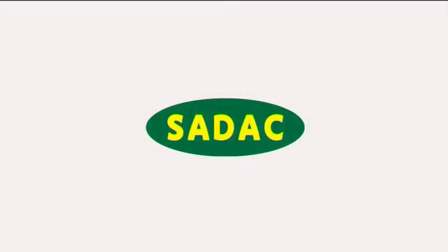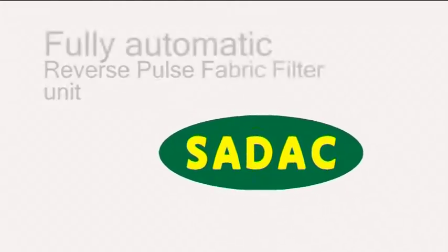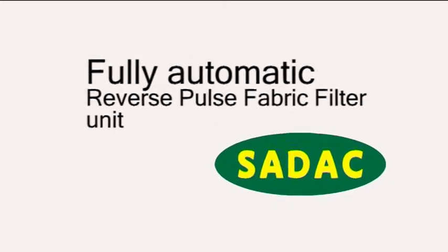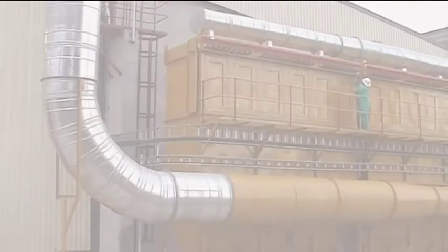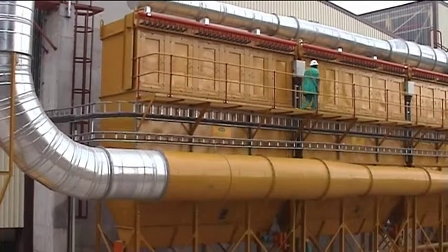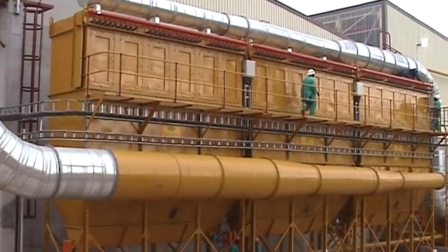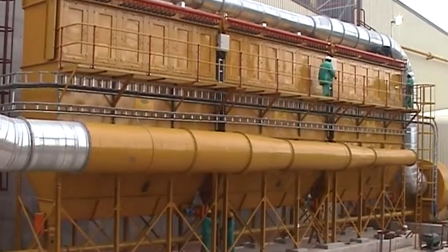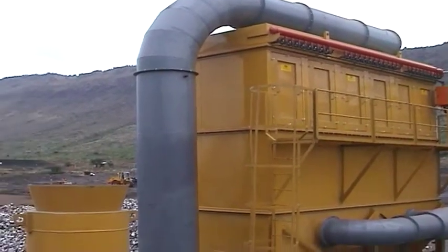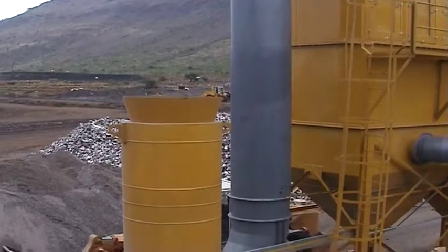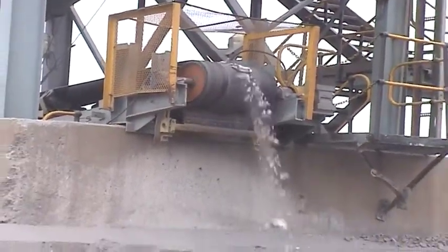The primary and most efficient dry filtration and dust collection equipment is the Sadac fully automatic reverse pulse fabric filter unit. Commonly referred to as a bag filter unit, but uniquely advanced by design, construction methods and automation to suit each application. This unit is utilized for high dust loads, extended periods of operation and a demand to meet exhaust emission legislation. The reverse pulse filter is most suited to fine dry dust particulate with filtration efficiencies peaking at 99.9% at 5 microns.